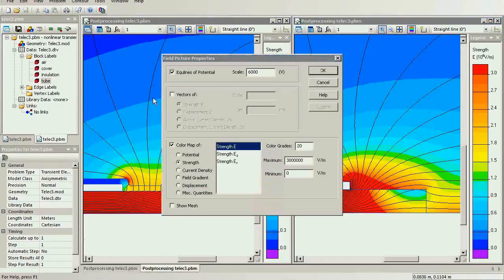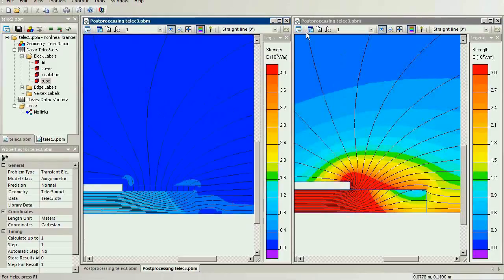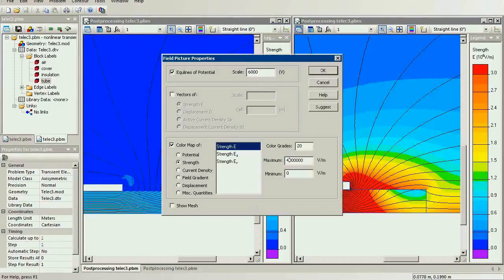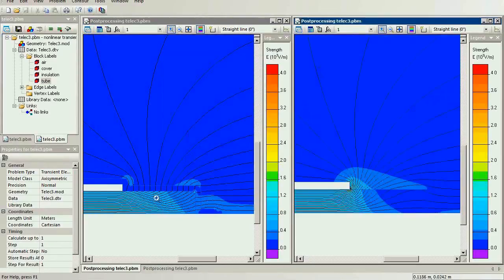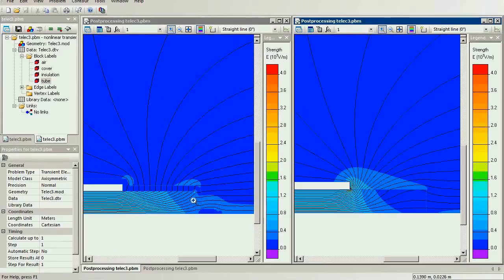Let's again adjust the field picture and take a look at the area where the stress is above the breakdown voltage of the insulation. You can see nothing critical for the cable insulation in both cases. So the stress control tube allows to reduce the electric field stress in the air, and at the same time it doesn't affect the electric field stress in the insulation. The electric field stress in the insulation stays on the low level.